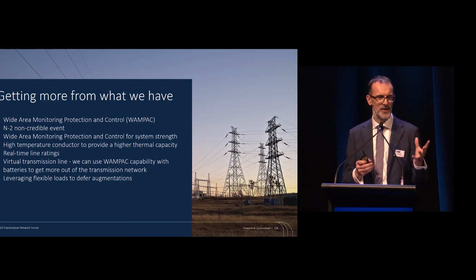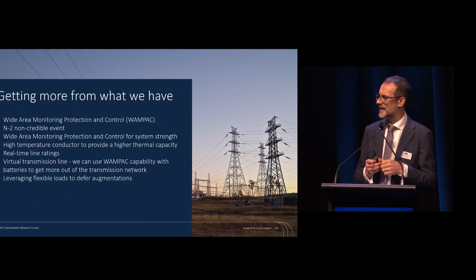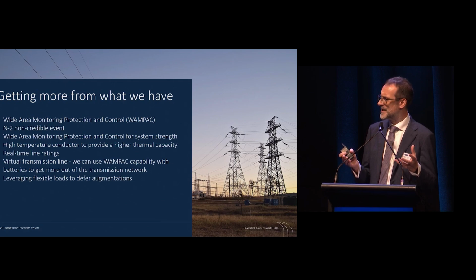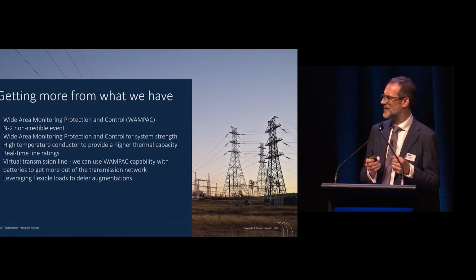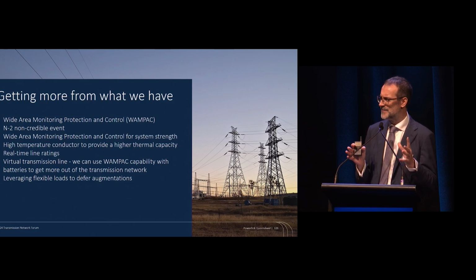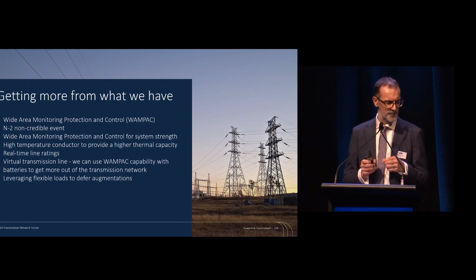High temperature conductor - been looking at that for some of our REZs. A 275 kV high temperature REZ with a little bit of curtailment can get 4,500 megawatts of hosting capacity. So we see that as a good sweet spot for connecting renewables.